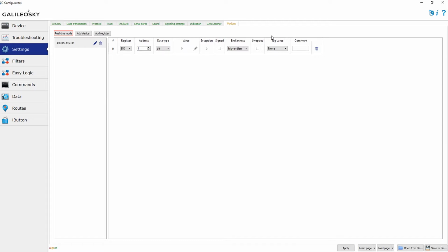The register parameters must be specified in the documentation for the connected equipment. When setting up the sensor registers, please note that different manufacturers can start numbering from either register 0 or first. Typically, different sensors transmit several parameters in different registers. In this case, you'll need to create a register for each of the parameters that you want to read. So, we set up the register.